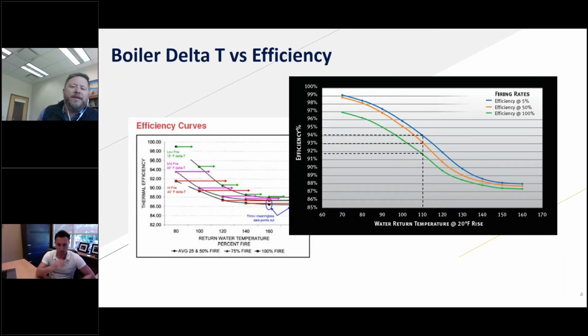When we look at that, if we have a system that wants maybe 120 degree hot water, as we've driven that down, maybe we have a 30 or 40 degree rise to try to take advantage of that. We're making that wide delta T. And again, that's a function of this: as we reduce the water temperature returning to the boiler, it makes itself more efficient.